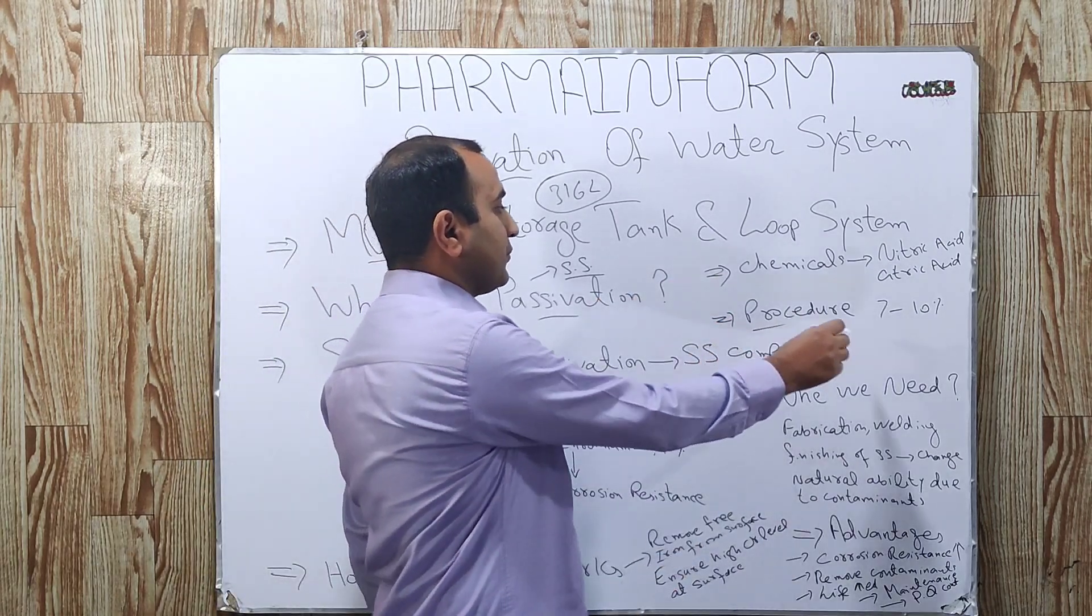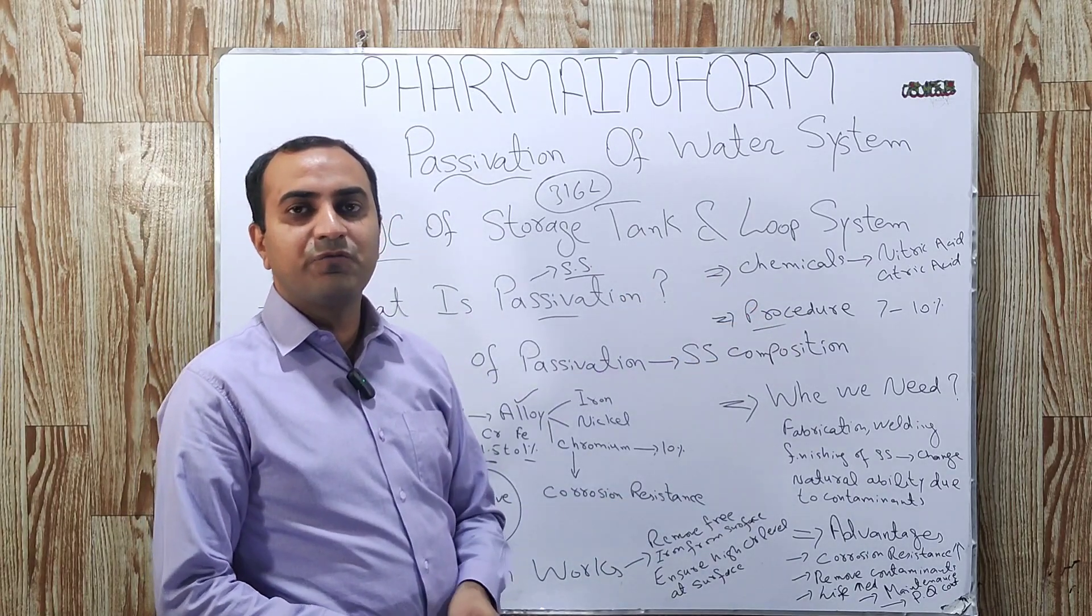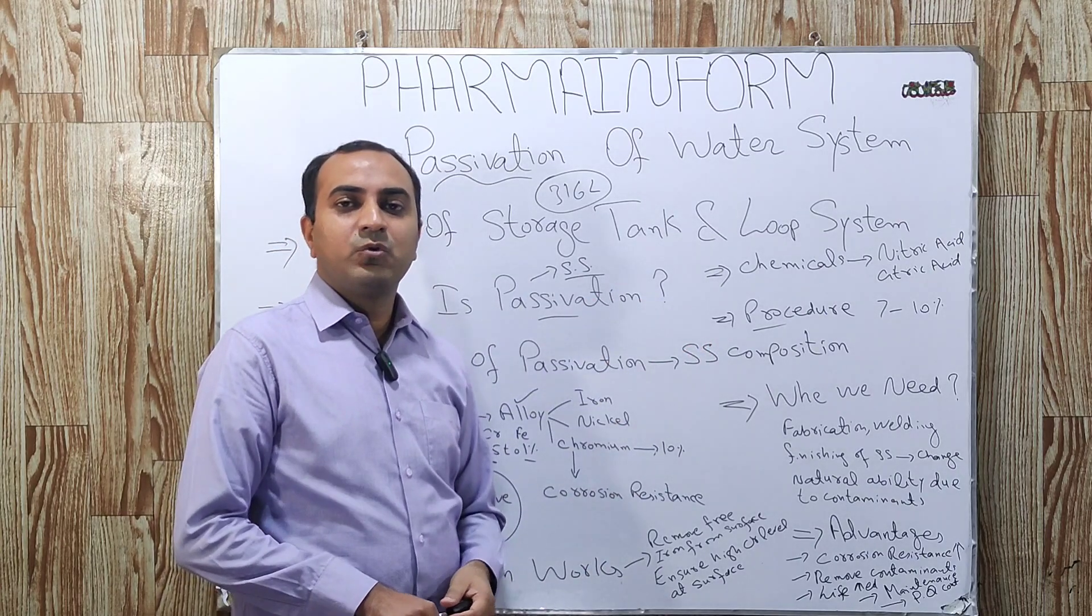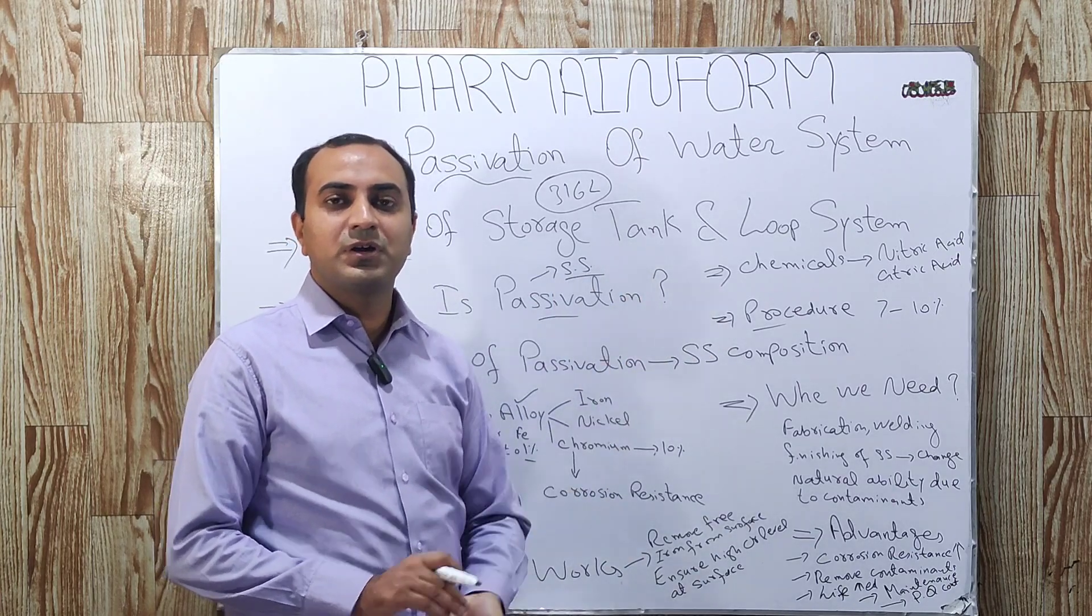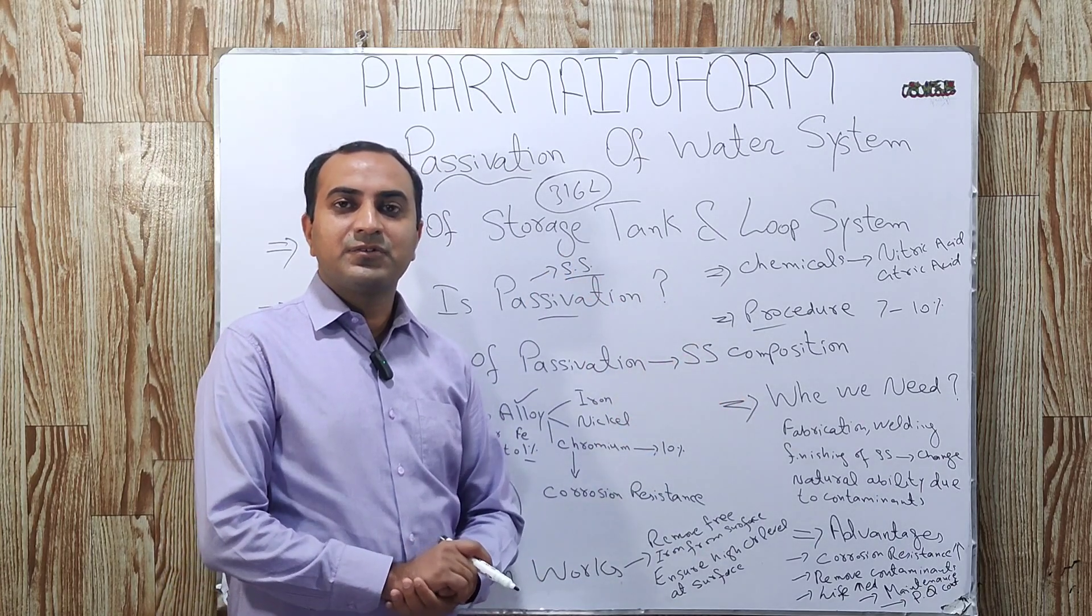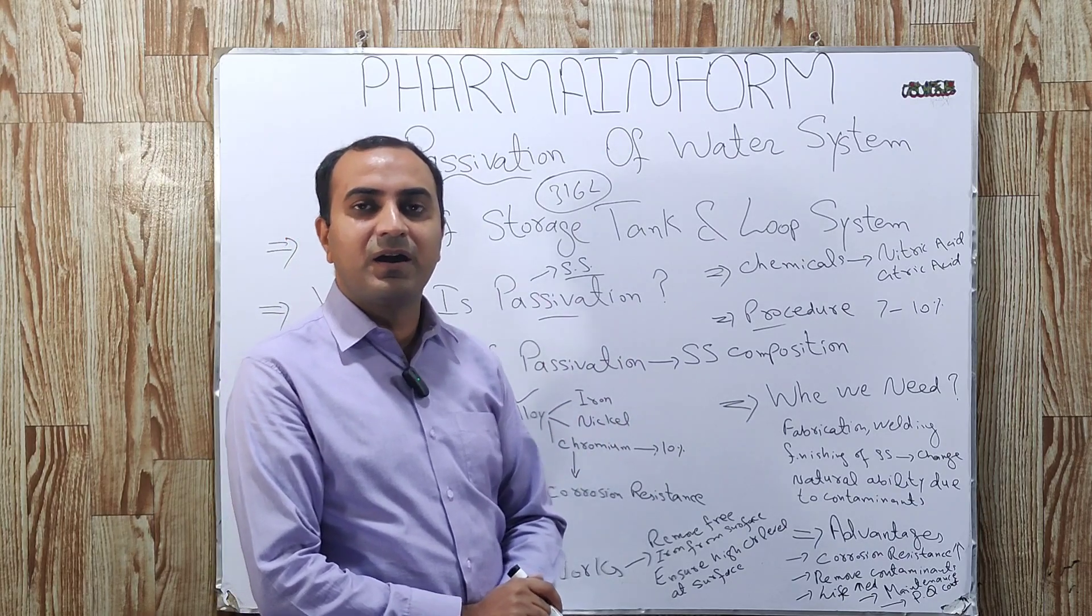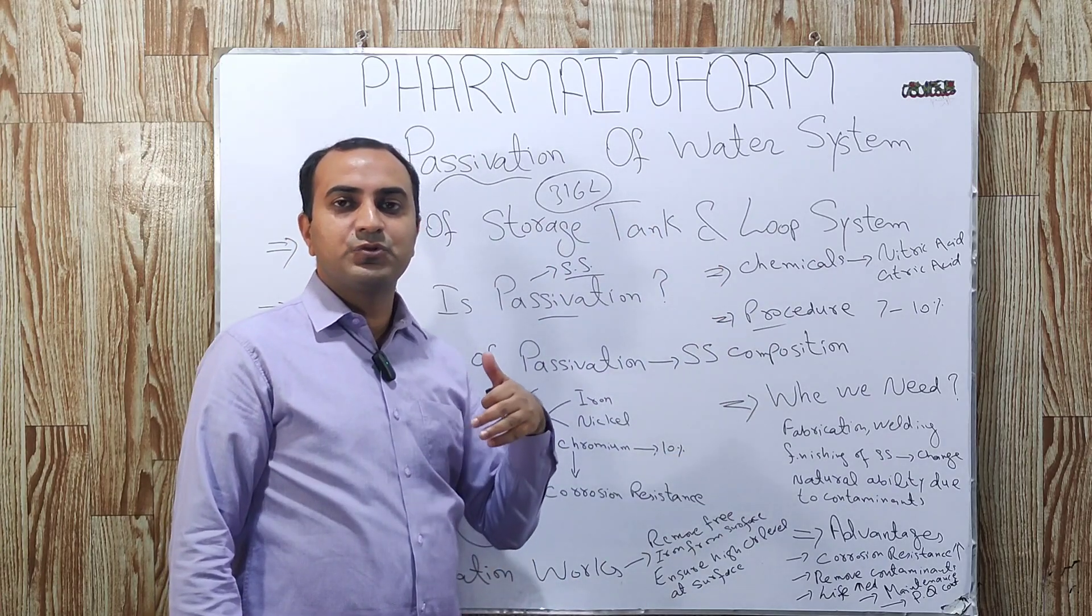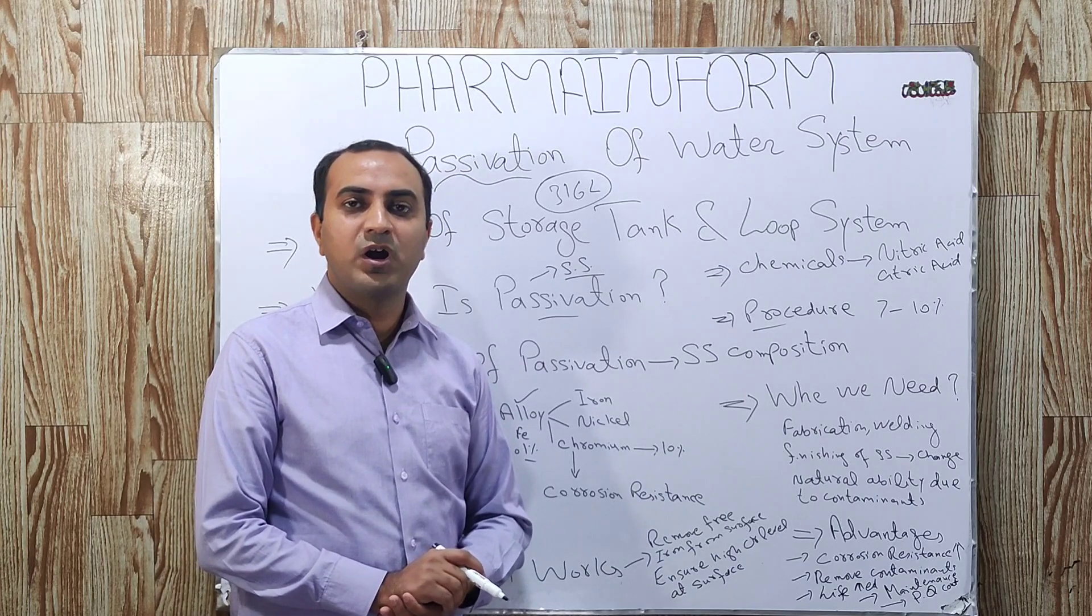Now, most important, what is the procedure of passivation? Generally, we use 7 to 10% of nitric acid. First of all, we prepare 7 to 10% solution of nitric acid as required according to the capacity of our storage vessel. We add nitric acid solution in the storage vessel and close all the user end valves and circulate this nitric acid solution from the storage tank through all the loop circulation system for 2 hours.